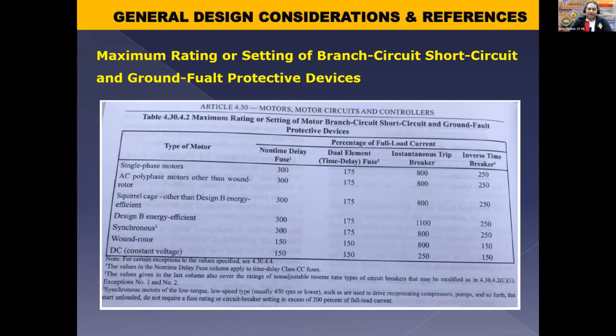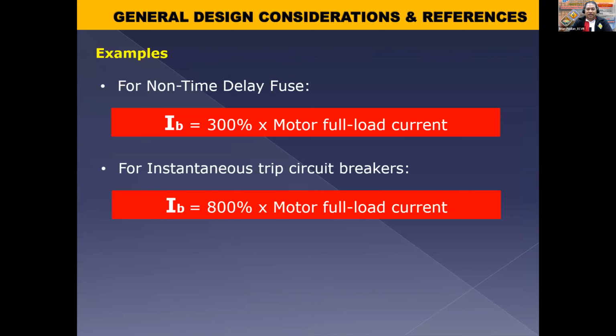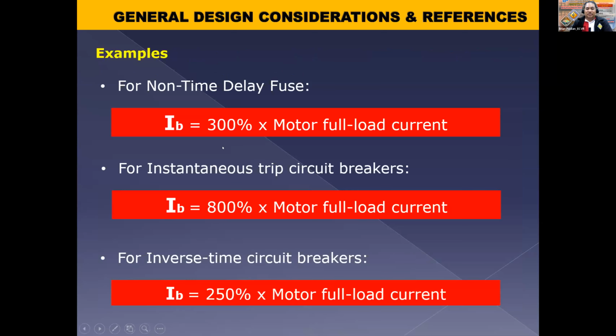Okay. Sige. So, examples lang ito kanina yung discuss natin, no? As long as hindi lang lagpas ito yung maximum multiplying factors natin, ha. But again, especially for larger motors, no, yung mga malalaking motors talaga na hindi ka na certain na yung i-assume mo na multiplying factors is coordinated ba talaga, then you have to do coordination study.